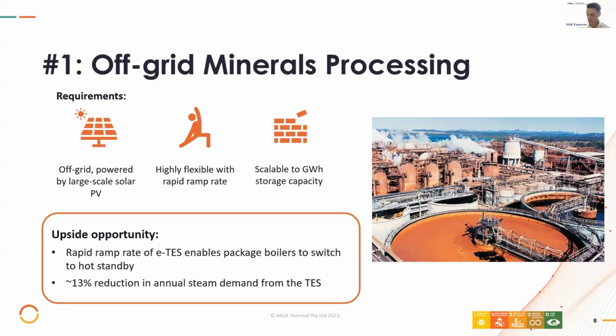Now, when we look at thermal energy storage, we can ramp up steam generation rapidly, about 25% of nameplate capacity per minute. That's far more rapid than traditional or incumbent package boilers. Ultimately, that means we can turn those package boilers off minimum turndown to hot standby, saving that 20 tons per hour of steam demand, and use our TES unit to respond rapidly to any contingency event that occurs. That in and of itself drives a 13% reduction in the annual steam demand from the TES, so a significant chunk.